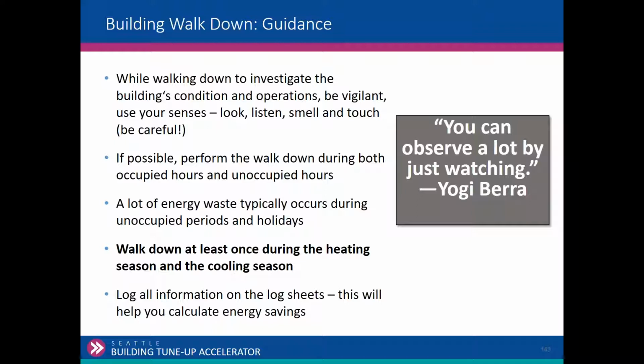A lot of energy waste occurs during unoccupied periods. For those that have interval data on your building, what is the demand of the building? What is the energy consumption when it's unoccupied? Or we've had some holidays come up. We've got a holiday coming up on Monday. Does the building get a holiday? Are the holidays programmed and scheduled into the schedules? That's something that's fairly easy to let slip and people not update their holiday schedule for the next year. And so their building's running full out on Thanksgiving Day, Christmas Day.